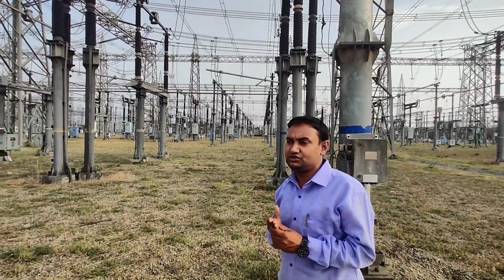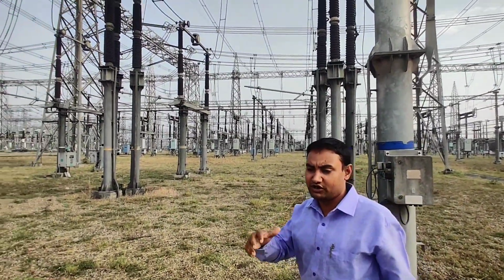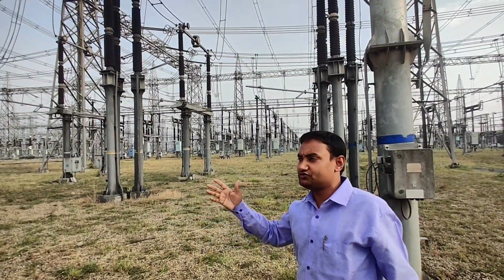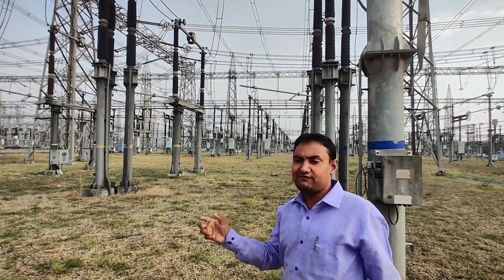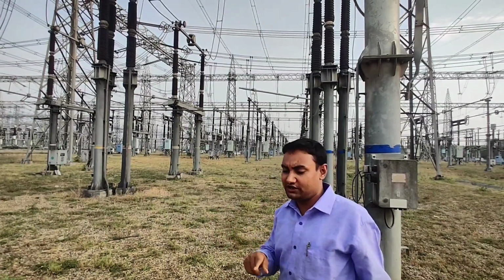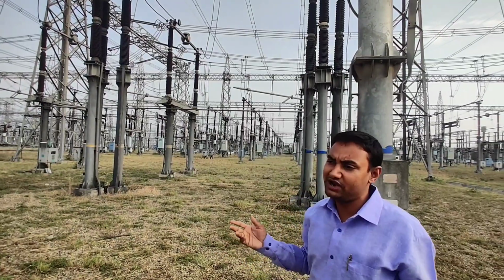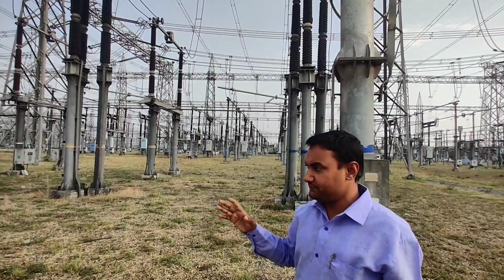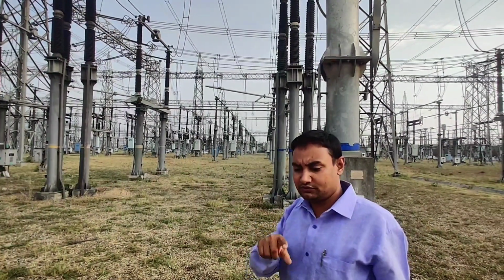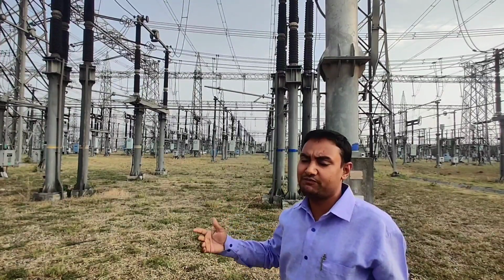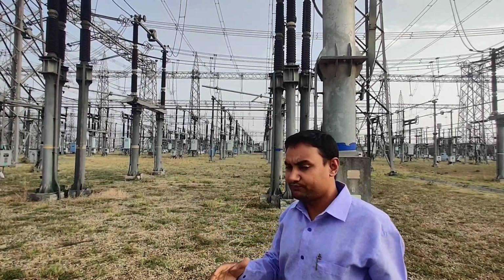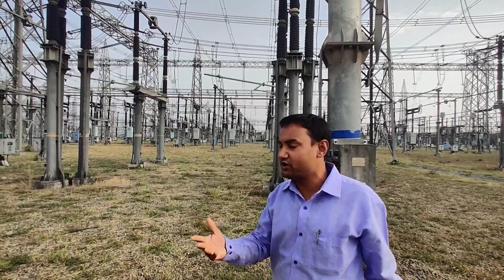Basically the CVT is used firstly for reducing that voltage of 400 kV to a measurable voltage of 110 volt, or in terms of phase to ground 63.5 volt, because such lower voltages are more suitable for measurement and also more suitable from the safety point of view.